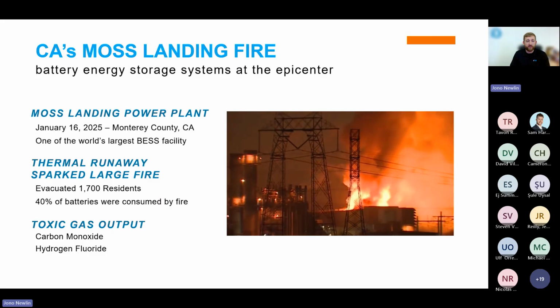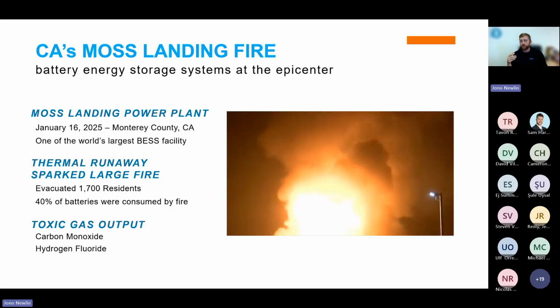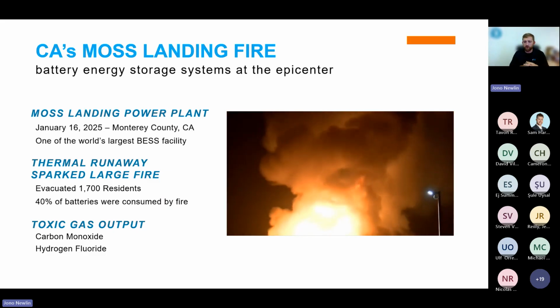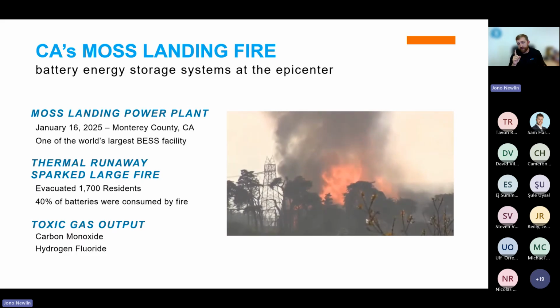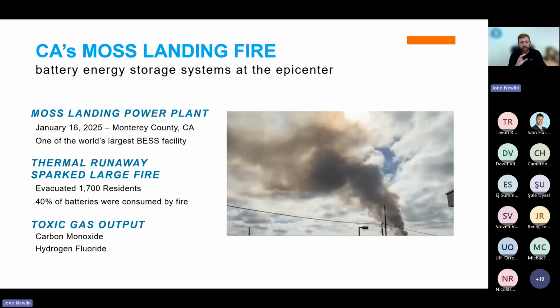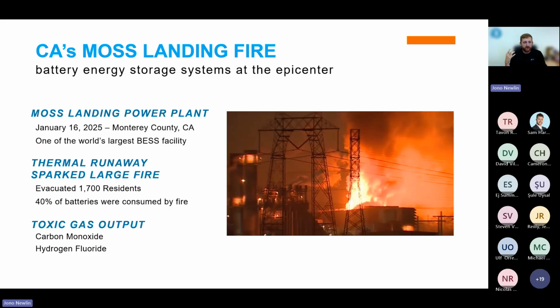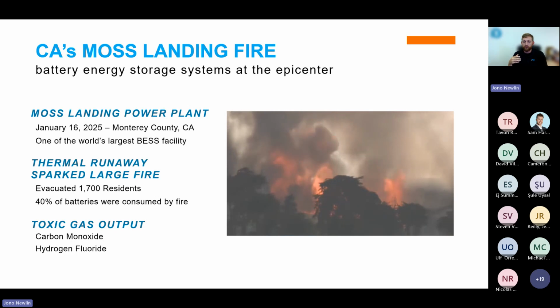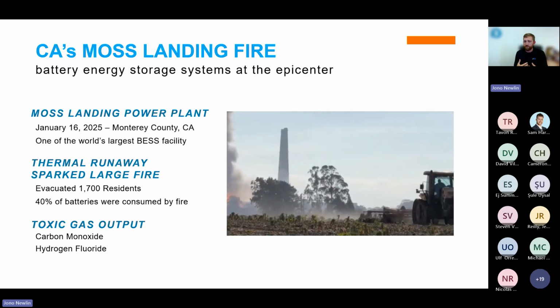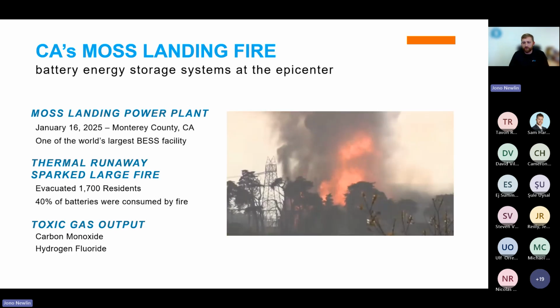The Moss Landing power plant used NMC batteries, an older system from around 2014. It was deployed indoors, and one failure at the cell level cascaded into a 300 megawatt-hour burn. The smoke you see is not typical smoke from a normal fire.